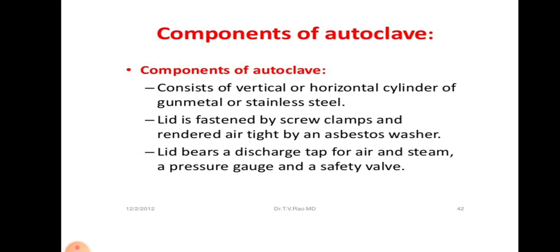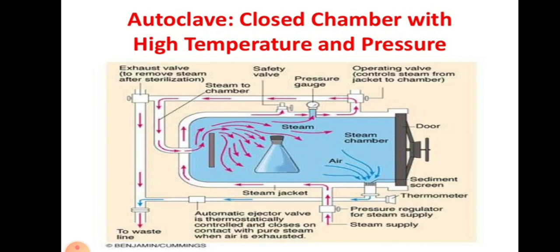Components of the autoclave: it consists of a vertical or horizontal cylinder of gunmetal or stainless steel. The lid is fastened by screw clamps and rendered airtight by an asbestos washer. The lid bears a discharge tap for air and steam, a pressure gauge and a safety valve. Here in the picture, you can see the lid at one end, the stainless steel chamber in which we keep all our media for sterilization, a pressure regulator for steam supply, a thermometer for checking the temperature, a pressure gauge, safety valve and exhaust valve to remove the steam after sterilization.